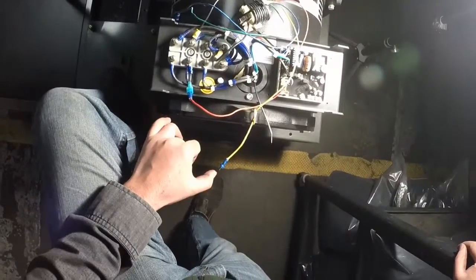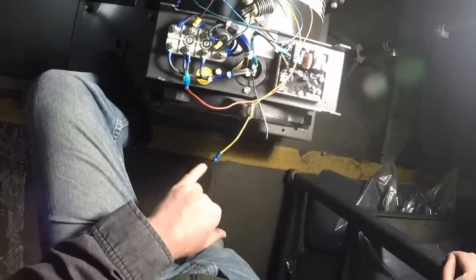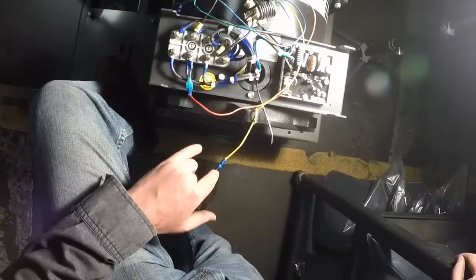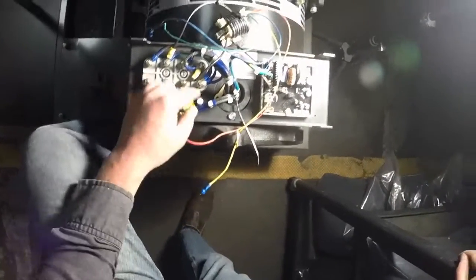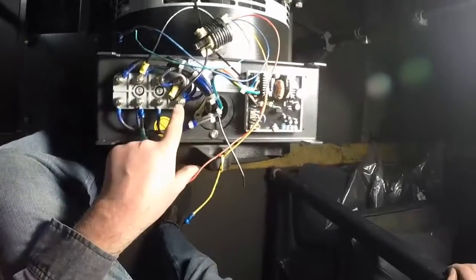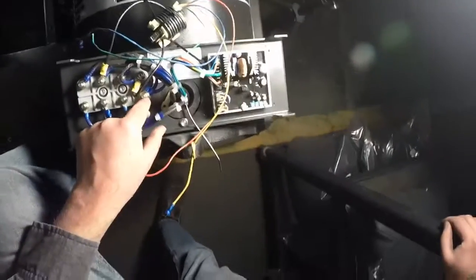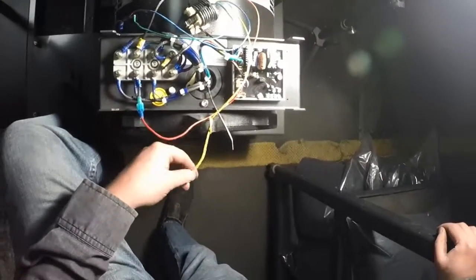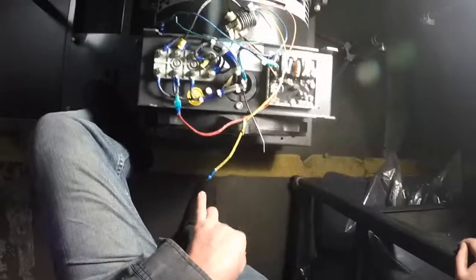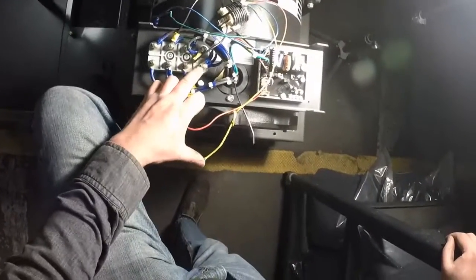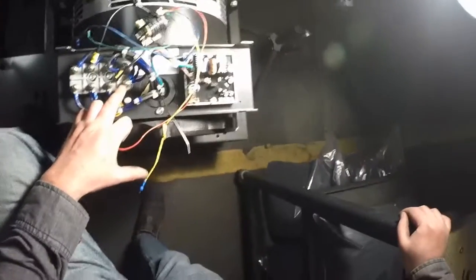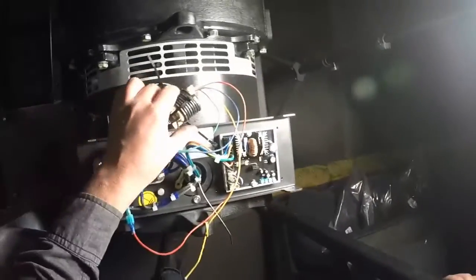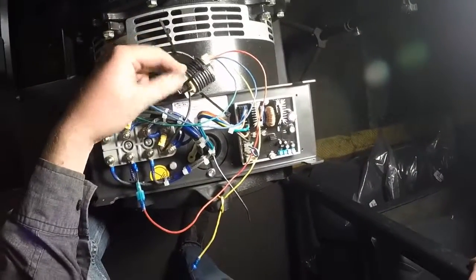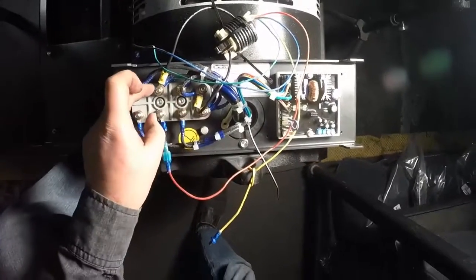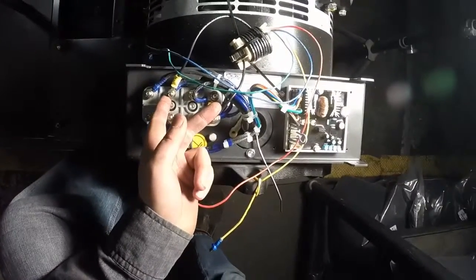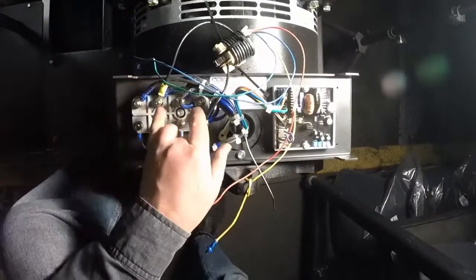So take a voltmeter, preferably with some alligator clips, connect it to this terminal, and then measure the voltage between this and your neutral on the generator, which is going to be connected to N2 here. Now measure that, and if you apply at least a few kW of resistive load to the generator, you should see the voltage here decrease. If it does the opposite and increases, then the polarity of this current transformer is incorrect. And the way you can fix that is just reverse the wires that are going between here and here, flip those around, and now your polarity should be the correct orientation.